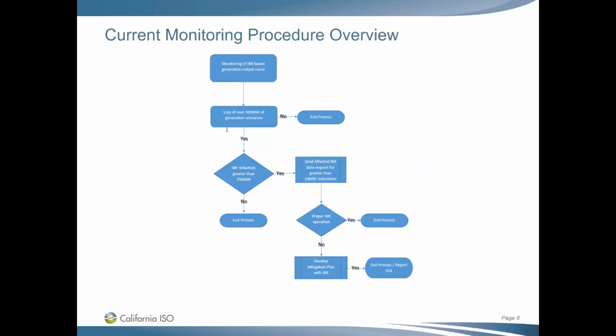We have a lot of large size and a lot of small size, so we have to put some type of a threshold. We monitor a loss of over 500 megawatt with regards to event analysis. If it is more than 500 megawatt, we always look at it.